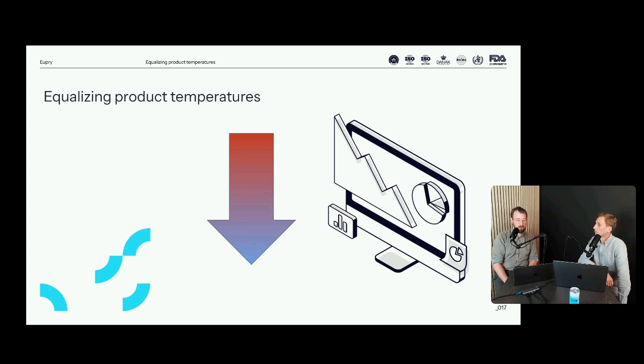There's a question here: no power failure or door opening test is recommended when external temperatures are between 15 and 25 degrees, but what about 30 to 35? That's a really good question. All standards and guidelines dictate the use of seasonal mappings, so it's a risk to run, from an auditor's perspective, not to do the opening test and power failure test, even when outside air temperatures are within limits. The question is, how much risk are you willing to take? I would definitely run a power failure and door opening test if you have temperatures between 30 and 35 degrees, because there might be other heat-producing equipment inside the warehouse whose effect during a power failure test you might not know.